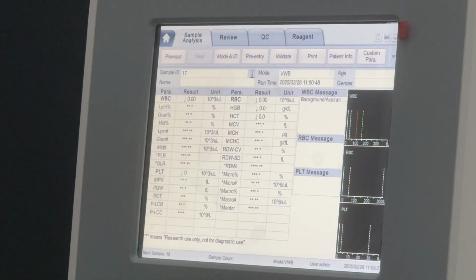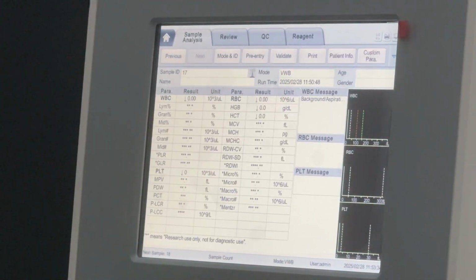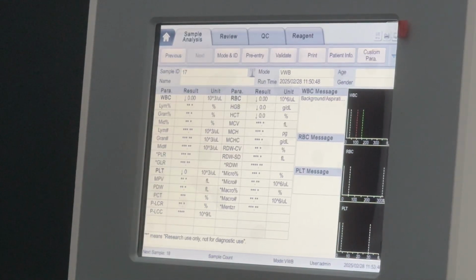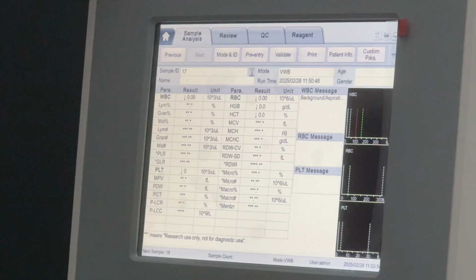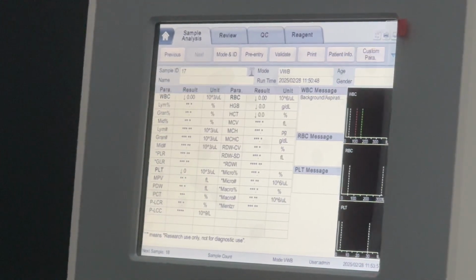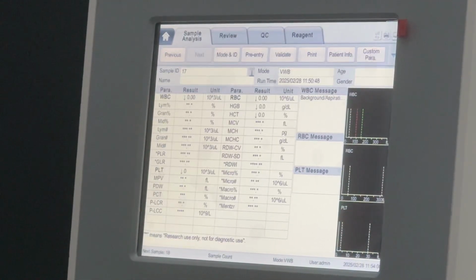Okay, before we run the sample, I need to go a little bit into the clinical side. Our analyzer has 29 parameters in total, of which 21 are reportable parameters and 8 are researchable parameters. Other brands in the market, when it comes to 3-part machines like this, only have reportable parameters and no researchable parameters. They have a minimum of 19, 20 or maximum 21. So we have 21 reportable parameters, but we have an extra 8 researchable parameters, so the total is 29 parameters.